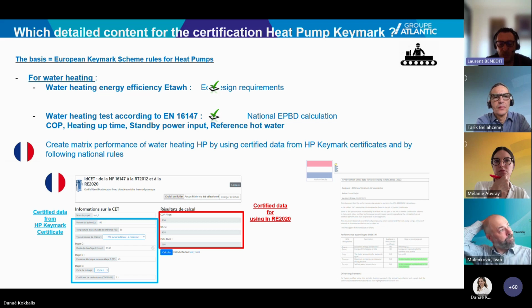So at the end, we get 3 useful values: COP for the domestic hot water, the thermal losses of the storage tank, and the energy input. And these 3 values can directly be used in the French EPBD calculation methodology.